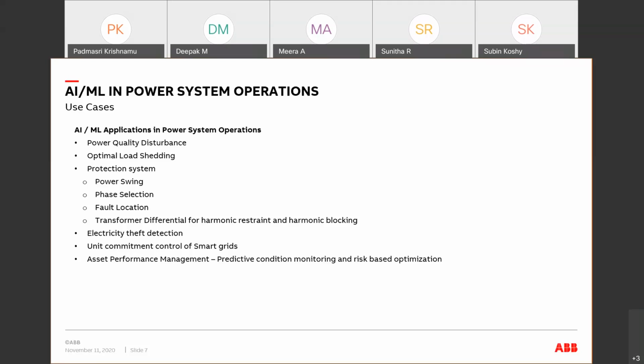The phase selection, we have always understood, especially when we are having auto reclosure for a single phase fault, and we want the system back in operation soon, requires phase segregated tripping. Meaning if it's a single phase fault, we want only that particular breaker to trip, and then also find out if it's a transient fault to get it back onto the system again. So this is something which we have always looked at as a big advantage. If you want this, there is a phase selection aspect which needs to be introduced into the distance protection. Invariably, phase selection reduces or adds to the time of operation of the relay.